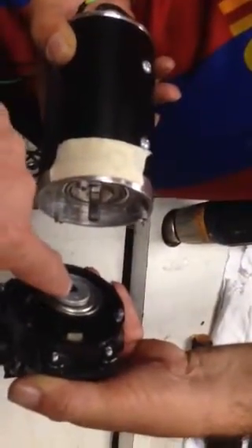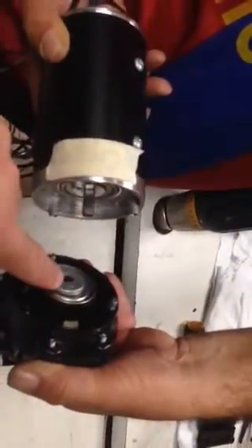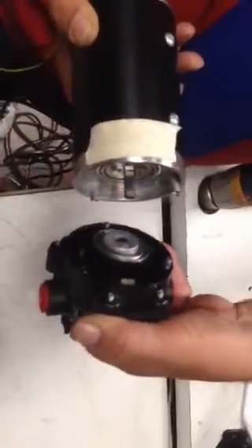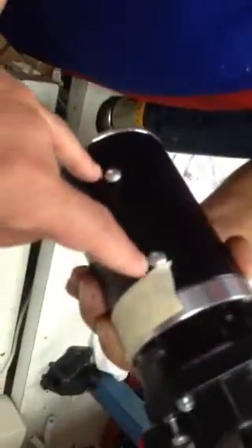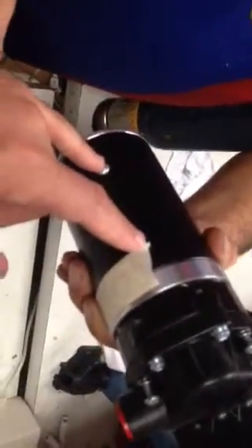Okay, we're ready to put the pump head onto the new motor. Now you look, there's a keyway, so you just need to align the keyway on the cam of the pump to the shaft. Now what you're going to want to do is you have the two holes here. This is where the base plate or the mounting plate is going to go. So of course you just want to line it up so that you have your pump head.